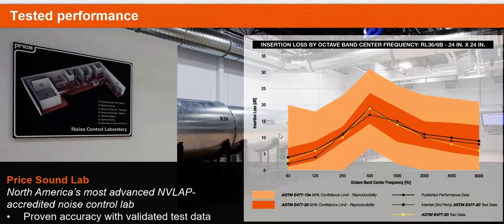Why was that? Well, the tolerances were a lot more flexible. So you could test on the black line and somebody could massage levels to the top of the light orange area. Acoustical consultants and engineers got tired of this. It's a bit of a mess out there in the industry for noise control performance. So we offer our state-of-the-art laboratory. We tested the silencers from all the competitors out there, at least the ones who wanted to, that were smart enough to participate in the round-robin testing.